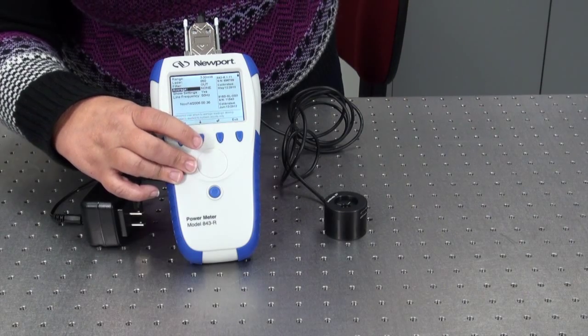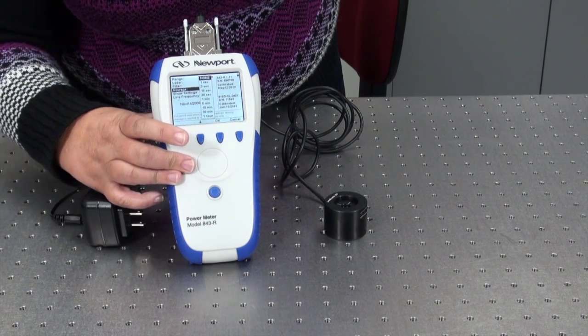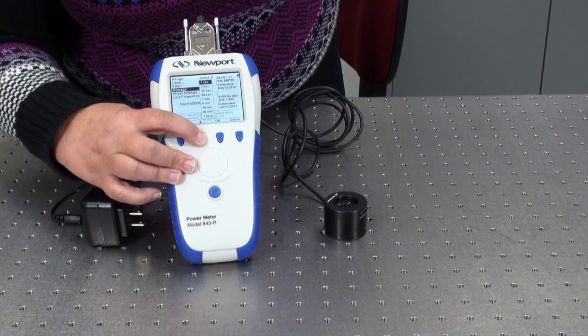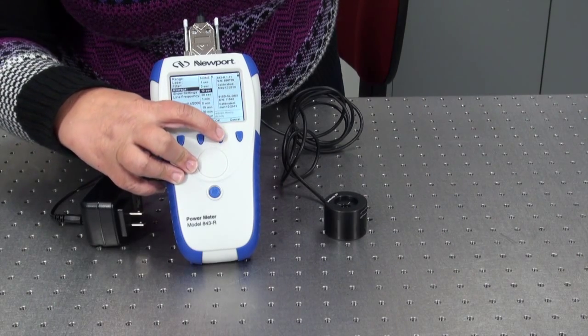The average menu is used to select the period of time ranging from one second to one hour, over which to average the measurements when measuring power. To set the average period, press the down arrow until the average menu is highlighted. Then press the enter arrow. Use the down arrow to scroll through the time period selections until you reach the one you desire. Press OK.